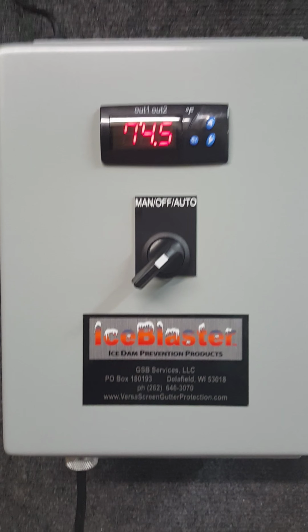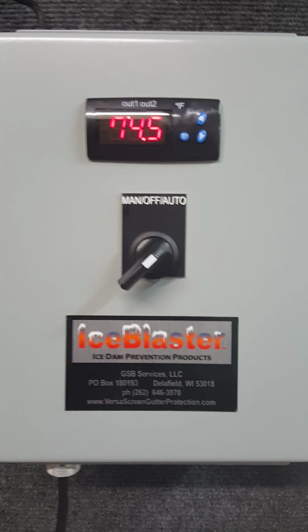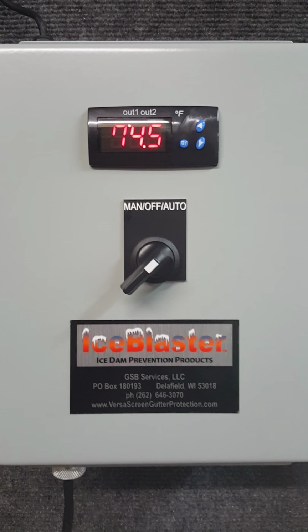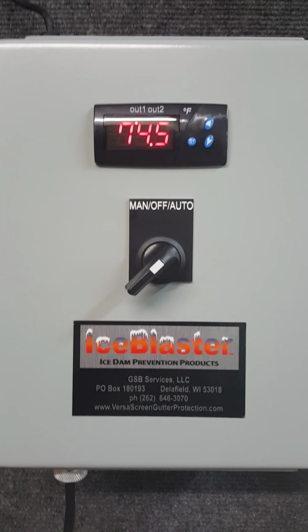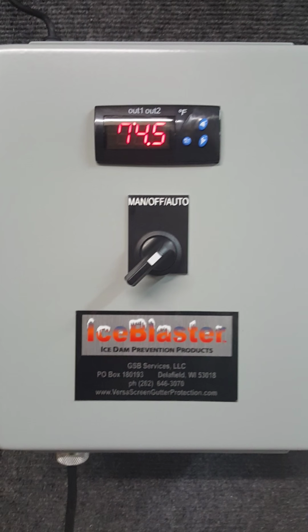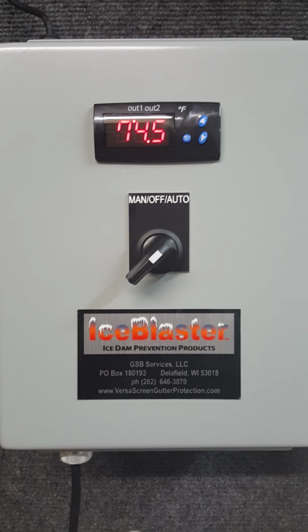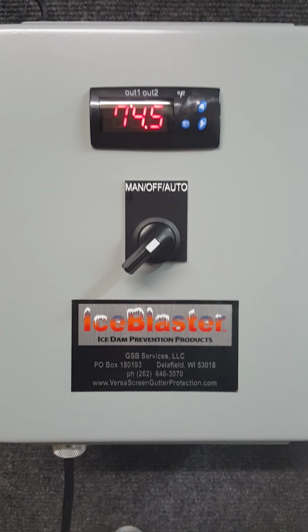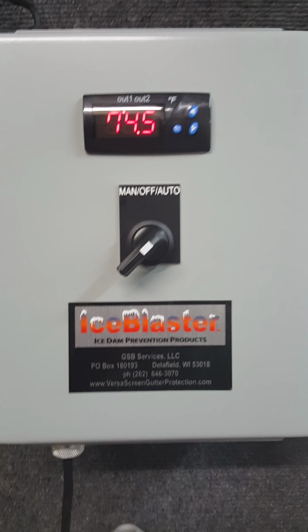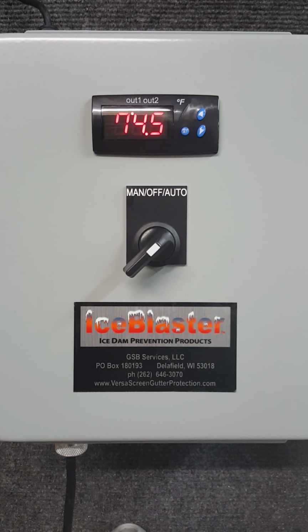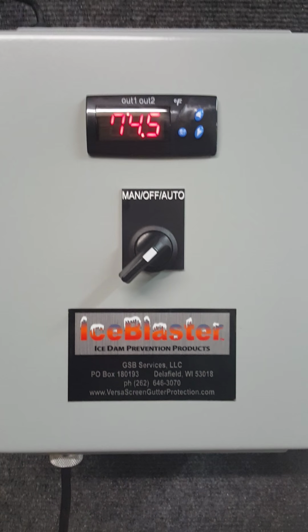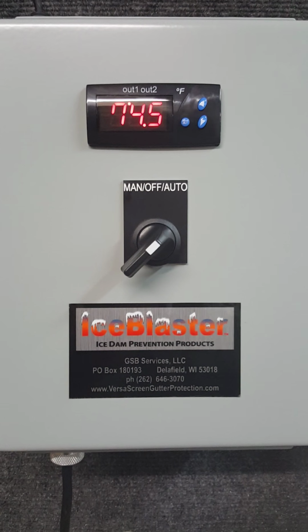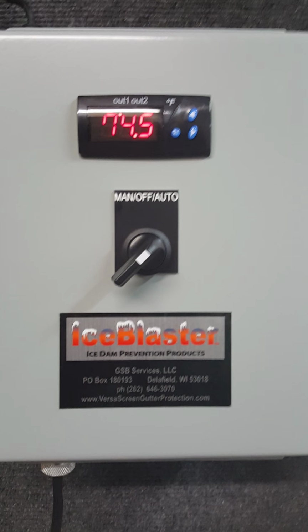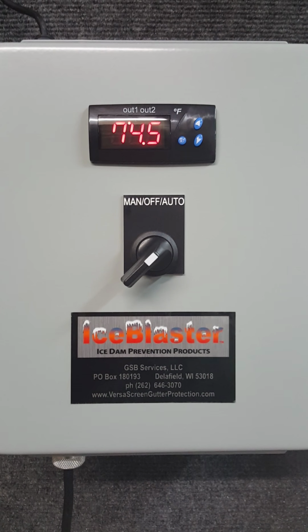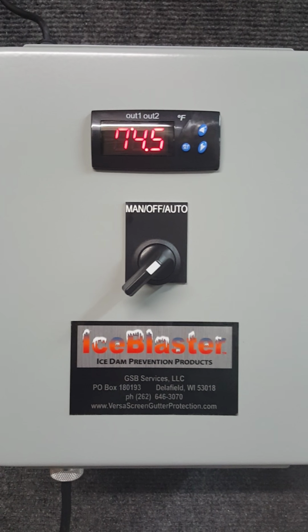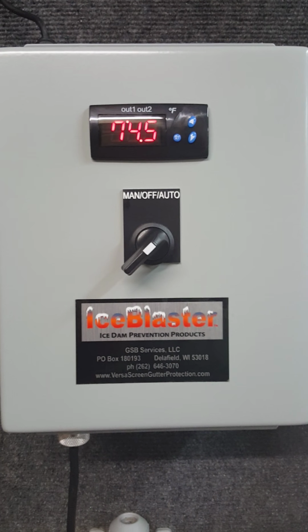So that's our DCAS4, handles up to 4 separate circuits, 240 volt max at 30 amps each circuit. So that's quite a large system that it can operate with just one panel, eliminating the need to have multiple thermostat controllers. We also have a companion to this, an 8-circuit controller that has 2 switches or 2 contactors in it. They each can handle up to 4 separate circuits, but one of the contactors is delayed by 2 minutes for its startup. And what that affords is you don't get the massive inrush when you split the circuits up that way and have that delay built in. So that's kind of a big help, especially on residential homes where these panels are very popular as well.